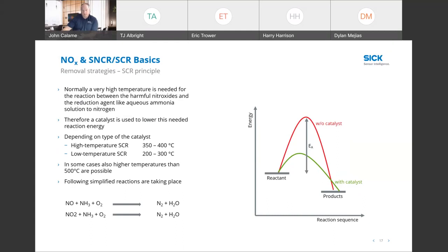Yep, good point, Dylan. It's imperative to be able to measure those low levels accurately and repeatably to provide the tightest, optimized performance of the SCR. Make sure that you're removing all the NOx, but make sure that you have enough. So it's kind of like the Goldilocks type thing. You don't want the porridge to be too cold or too hot. You want it to be just right. So this way you're able to optimize performance and reduce the amount of ammonia that's injected, and make sure you don't over inject and create an issue where you're damaging your catalyst.